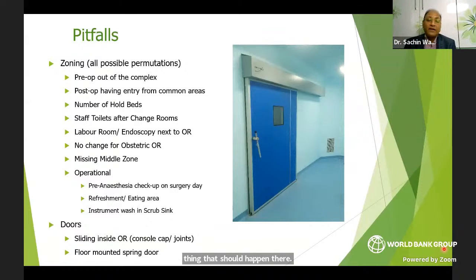We also have some conflicting views on doors. Sliding doors not only require the aperture for entry, which is your 5-feet width entry, but also equal and additional area for sliding it on the wall. Due to design, there is often a deficiency of space, so a lot of vendors slide the door inside the operating room, like in this adjoining picture. This is inside the OT, and the OT door is sliding inside. The only problem is that even with a console cap, there are a lot of joints in this. The OT door has its own motor, which requires a lot of grease, and a lot of channels and components which have to be outside the OT - they have to be avoided inside the OT.